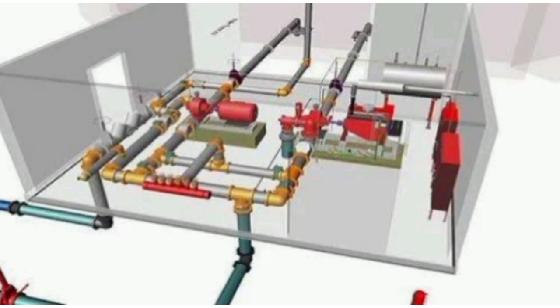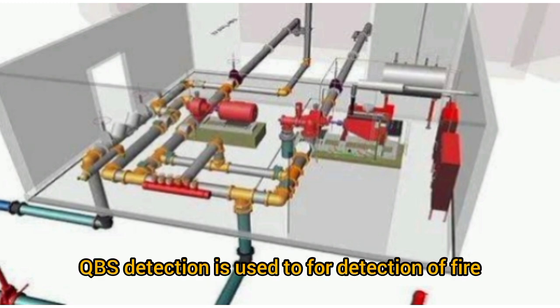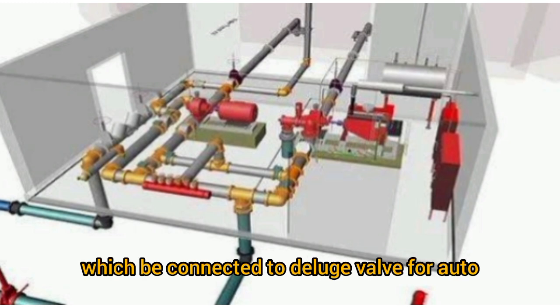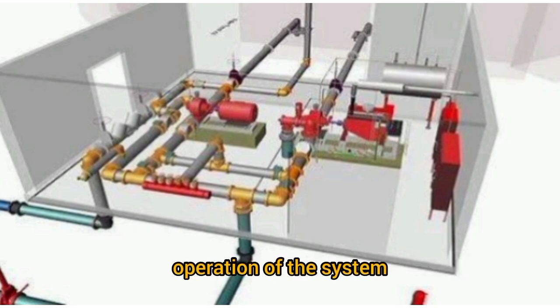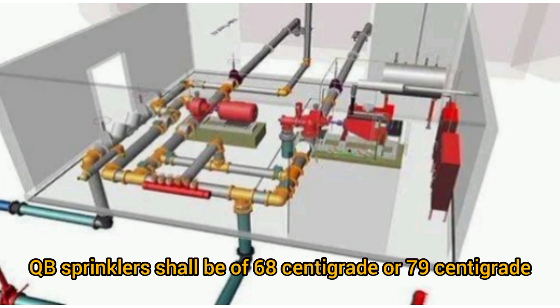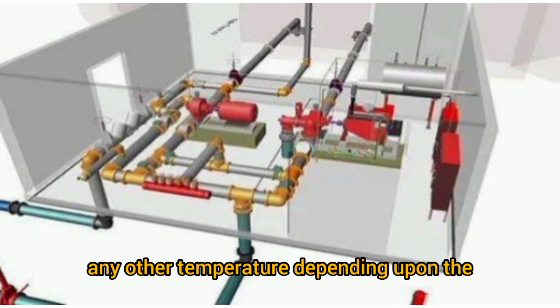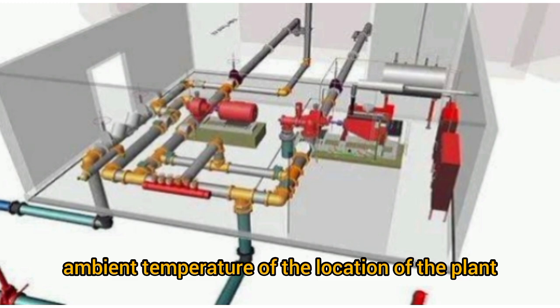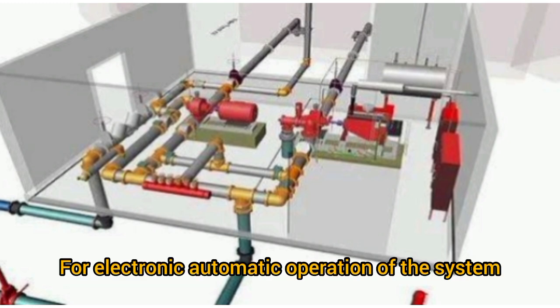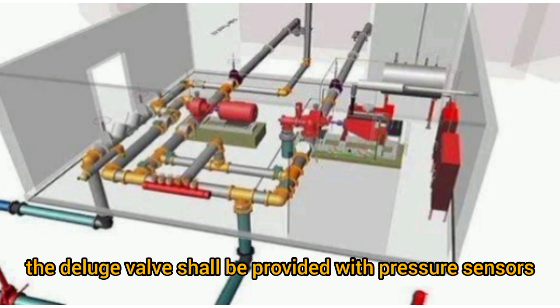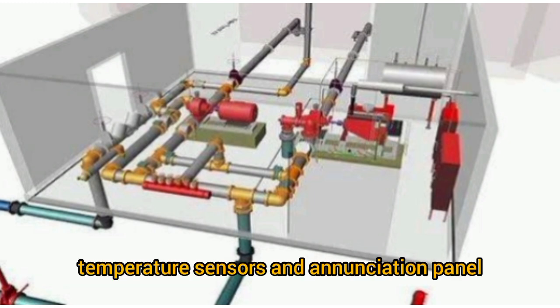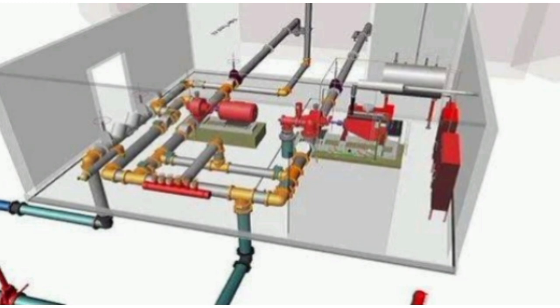How it works: quartzoid bulb sprinklers, QBS, are used for detection of fire and are connected to the deluge valve for auto operation of the system. QB sprinklers shall be of 68 centigrade or 79 centigrade, or any other temperature depending upon the ambient temperature of the location of the plant. For electronic automatic operation of the system, the deluge valve shall be provided with pressure sensors, temperature sensors and an annunciation panel.